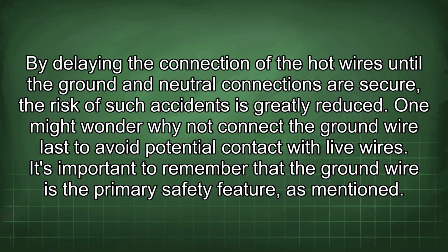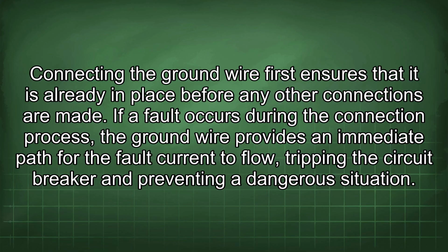One might wonder why not connect the ground wire last to avoid potential contact with live wires. It's important to remember that the ground wire is the primary safety feature, as mentioned. Connecting the ground wire first ensures that it is already in place before any other connections are made. If a fault occurs during the connection process, the ground wire provides an immediate path for the fault current to flow, tripping the circuit breaker and preventing a dangerous situation.